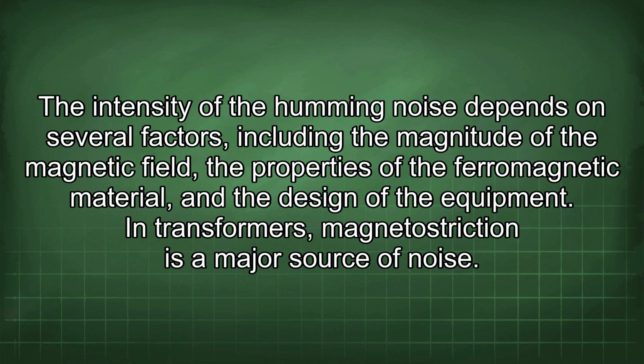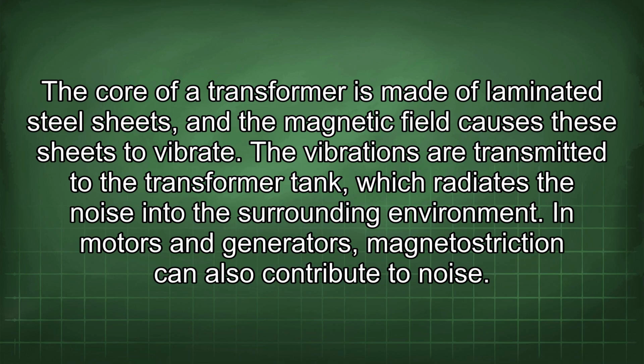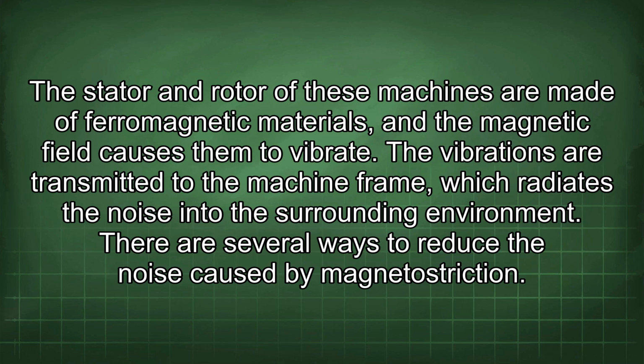In transformers, magnetostriction is a major source of noise. The core of a transformer is made of laminated steel sheets, and the magnetic field causes these sheets to vibrate. The vibrations are transmitted to the transformer tank, which radiates the noise into the surrounding environment. In motors and generators, magnetostriction can also contribute to noise. The stator and rotor of these machines are made of ferromagnetic materials, and the magnetic field causes them to vibrate. The vibrations are transmitted to the machine frame, which radiates the noise into the surrounding environment.